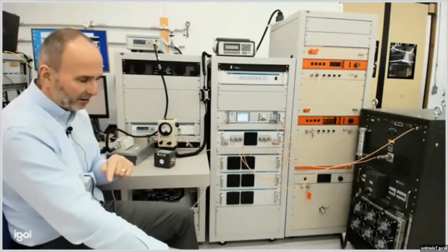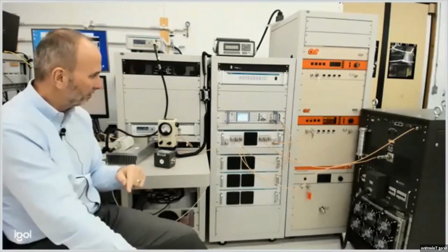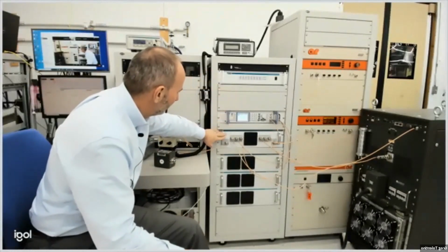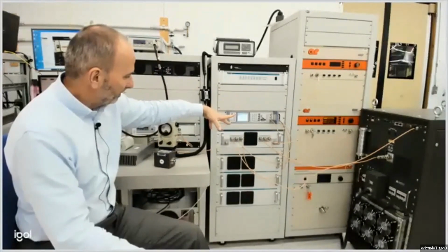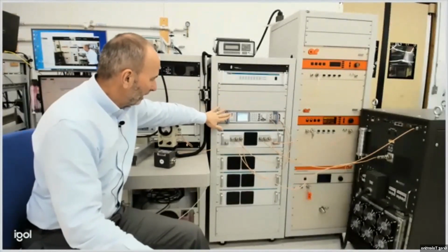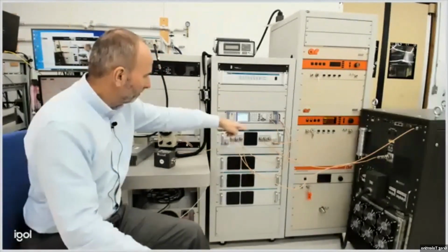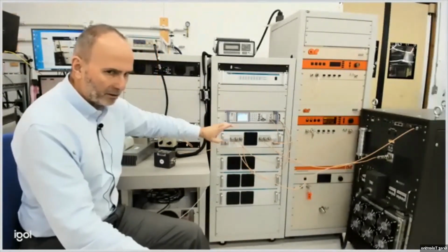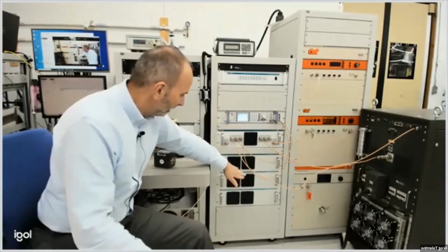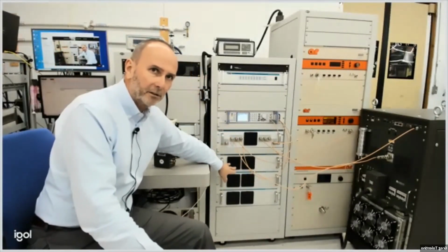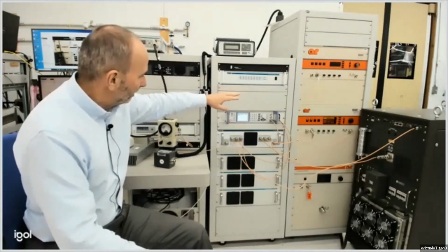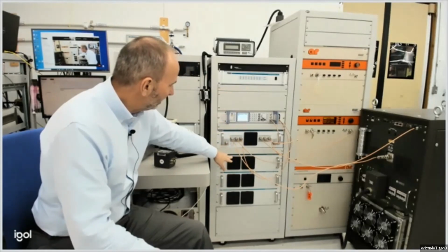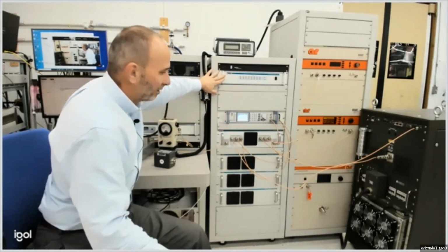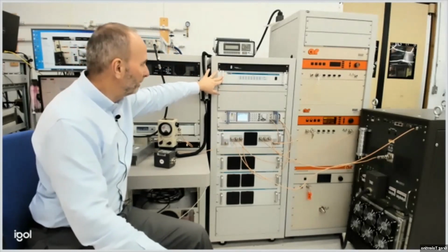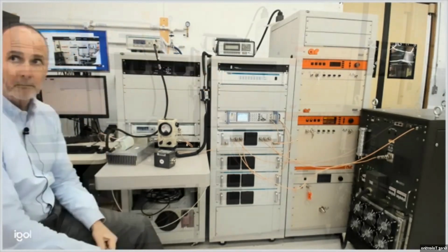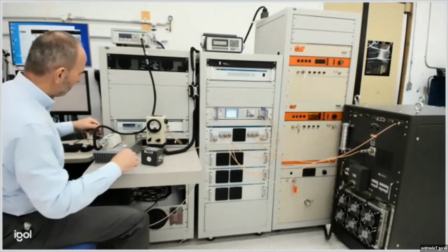Because amplifiers don't necessarily come in the same bands that filters do, we have the 1322A that independently lets you route the signal from the low power signal generator to 3 amplifiers, and then having got the high power signal back from one of the 3 amplifiers, can then route it to one of 3 chassis of filters. And which relays are selected here are determined by our 1320A relay driver box that's receiving a bit pattern from the software. So let's start with the calorimeters.